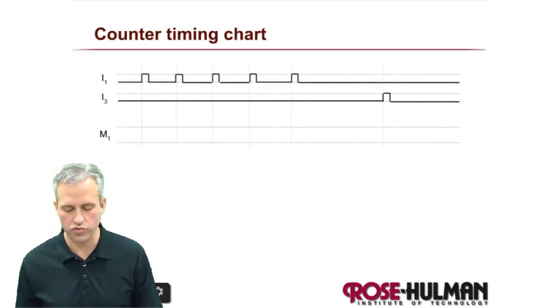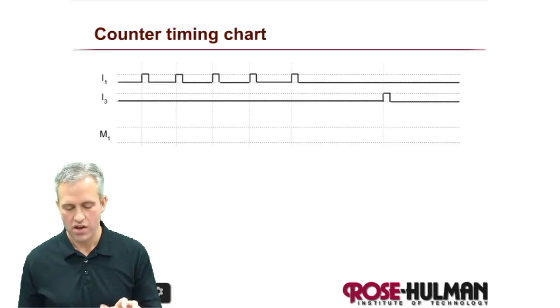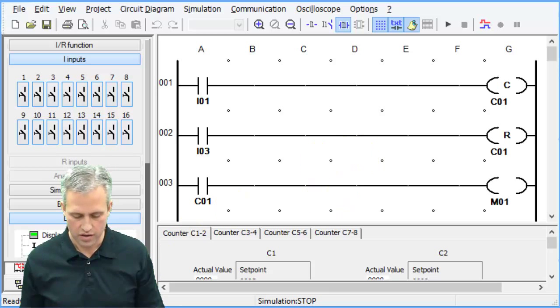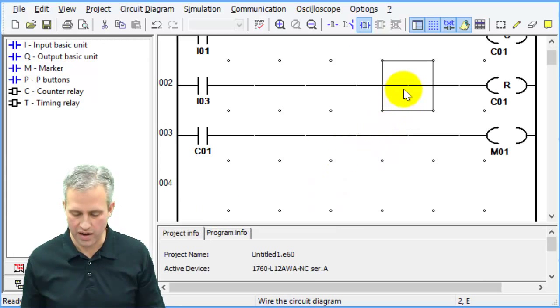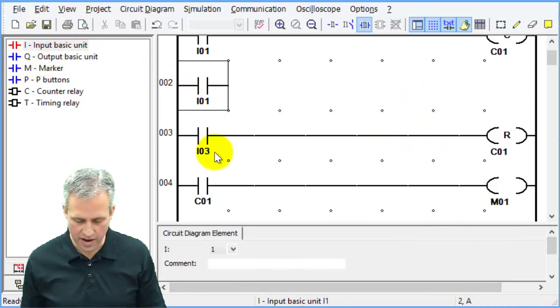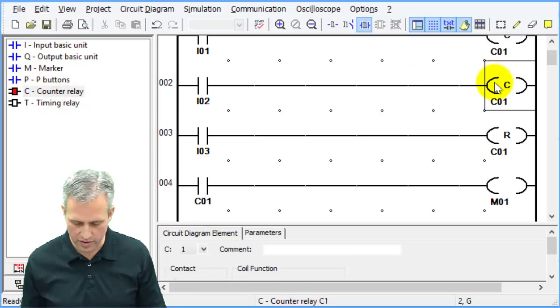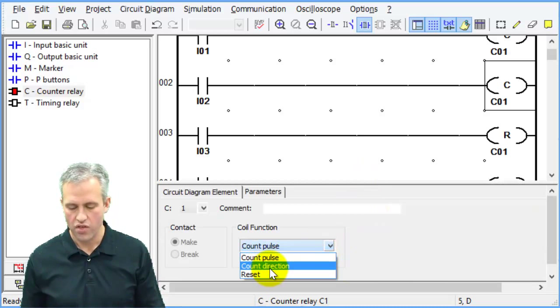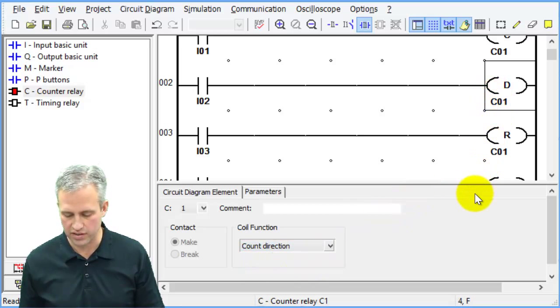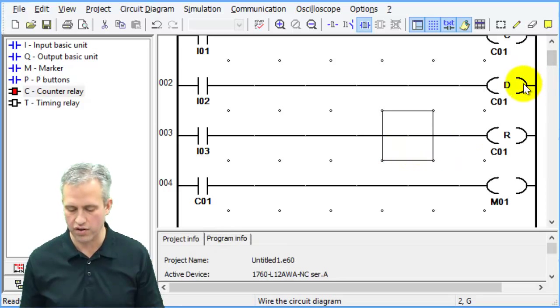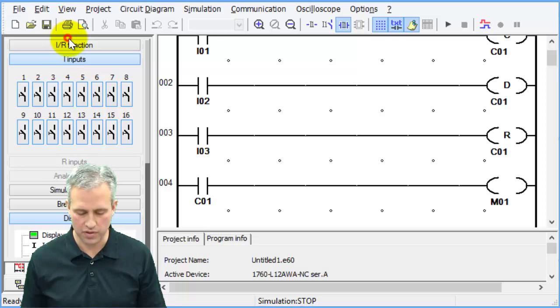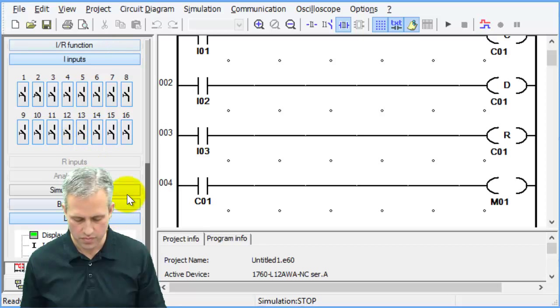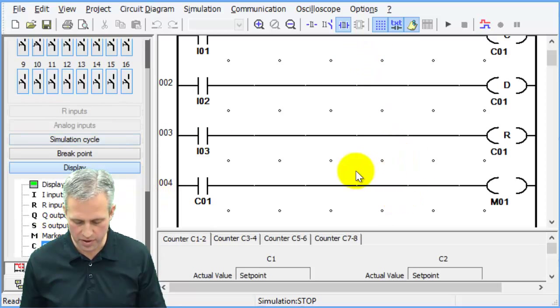These are the only true skills that you have to know about them for lab. Just because they're so easy, I'm going to teach you a couple other things real quick. Back to the circuit diagram. You may have noticed I did not use I2, so I'm going to add another rung here. You may have noticed that I did not use I2, so I'm going to have I2 controlling a counter as well. There's one more type of counter. There's pulse, there's reset, there's also a thing called direction. So you can see that it gets a nice D in it for direction. This is to let you change between counting up and counting down. So I'm going to go back into my simulation. I'm going to make I2 be a position just so it'll stay there.